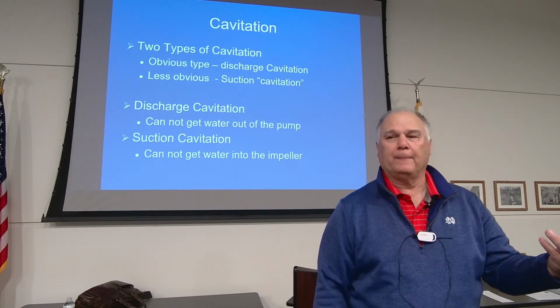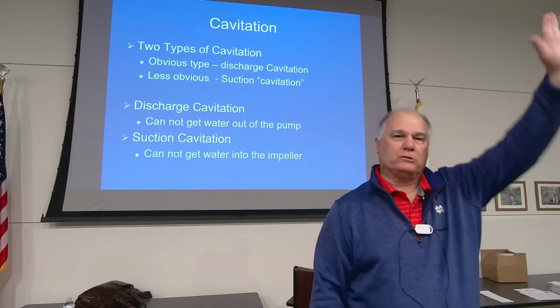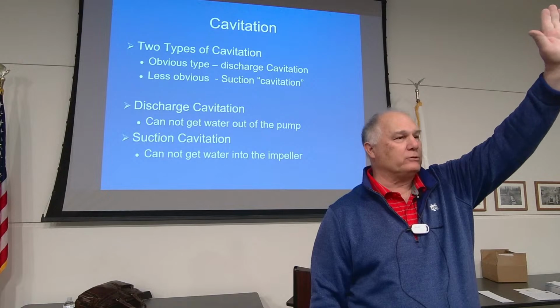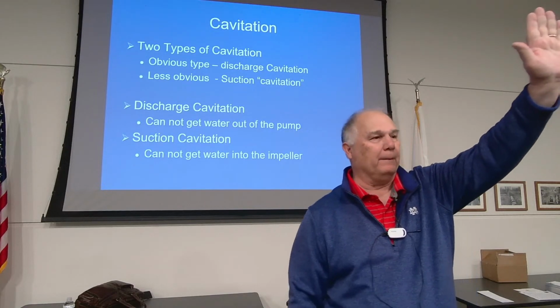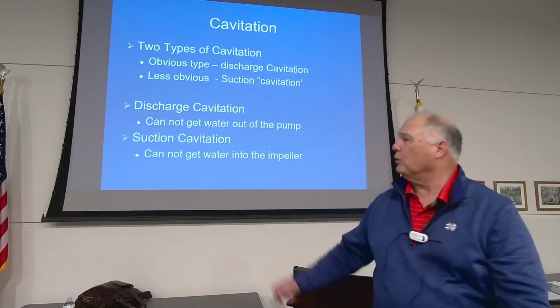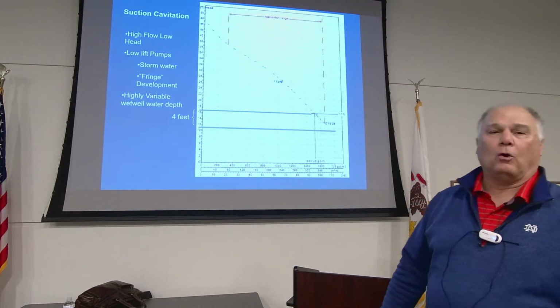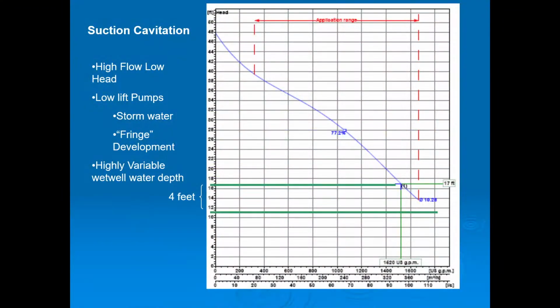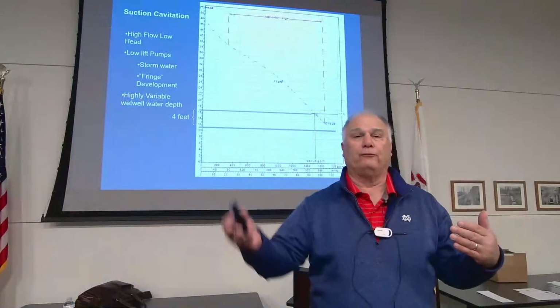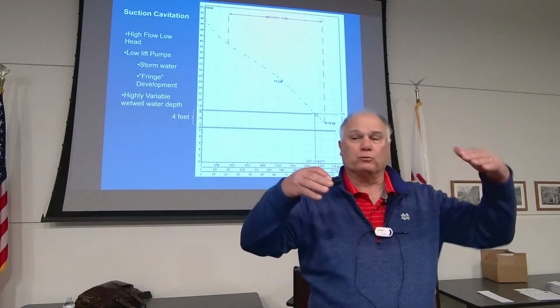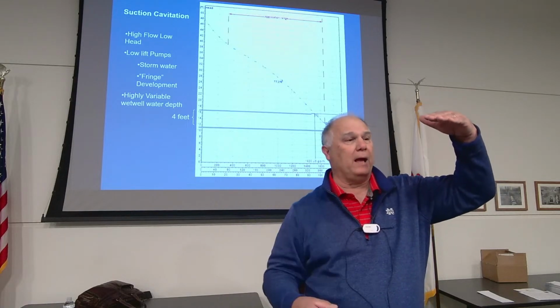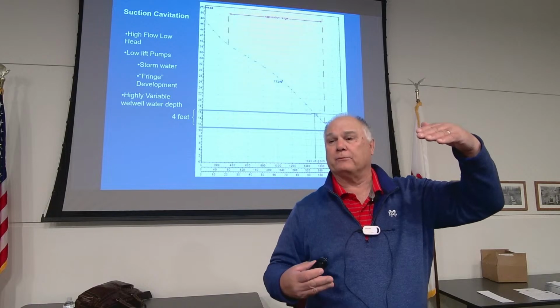It just depends. How many people have dry well, wet well stations, influent to treatment plants or anything like that, which is really where we see this come up, or in a collection system? We call it suction cavitation, or sludge holding tanks, or decant tanks, where the decant elevation may be 4, 5, 6, or 10 feet in that sludge tank. You've got to be careful of that when you select your pump. This pump usually doesn't run very much, but when it's full, you have less head because we're only pumping up a little bit, versus when it's down all the way to the bottom. When you shut the pump off, the head comes back.